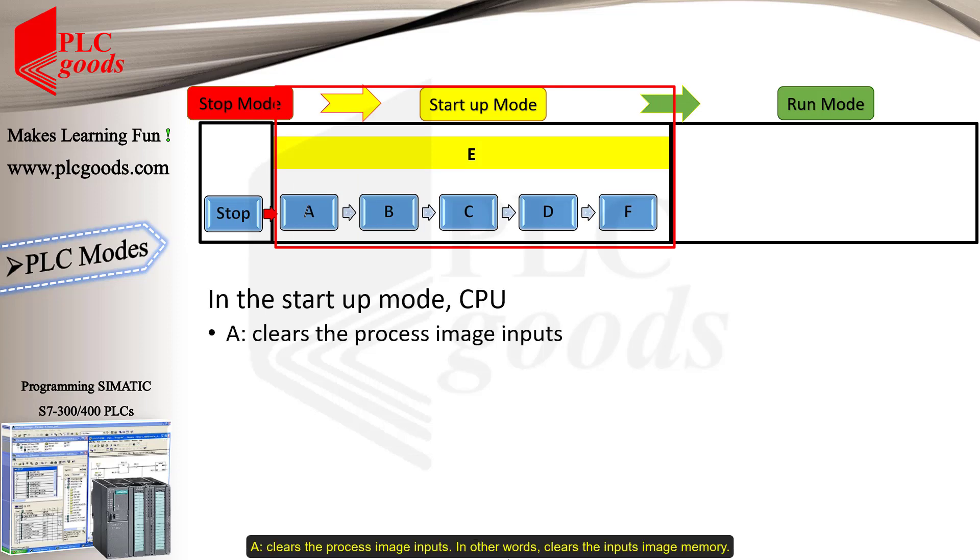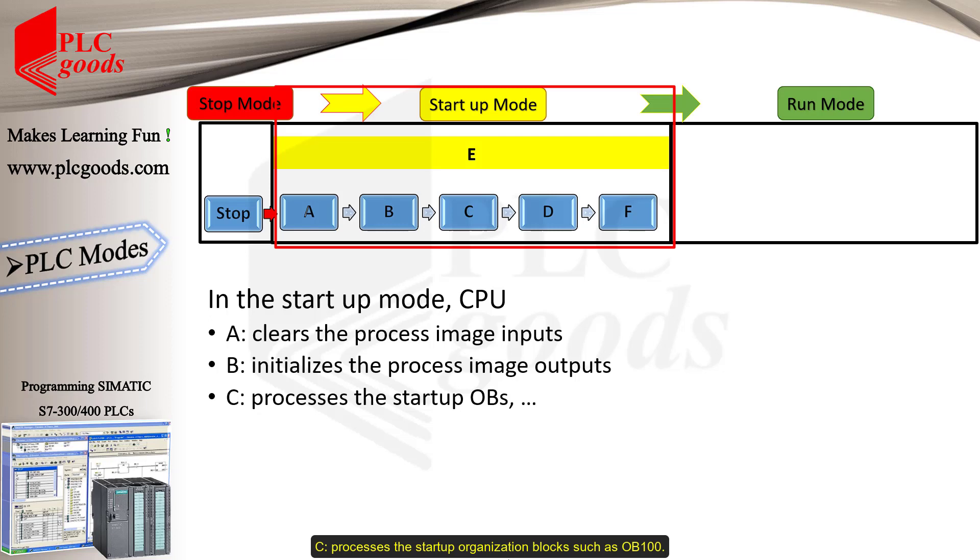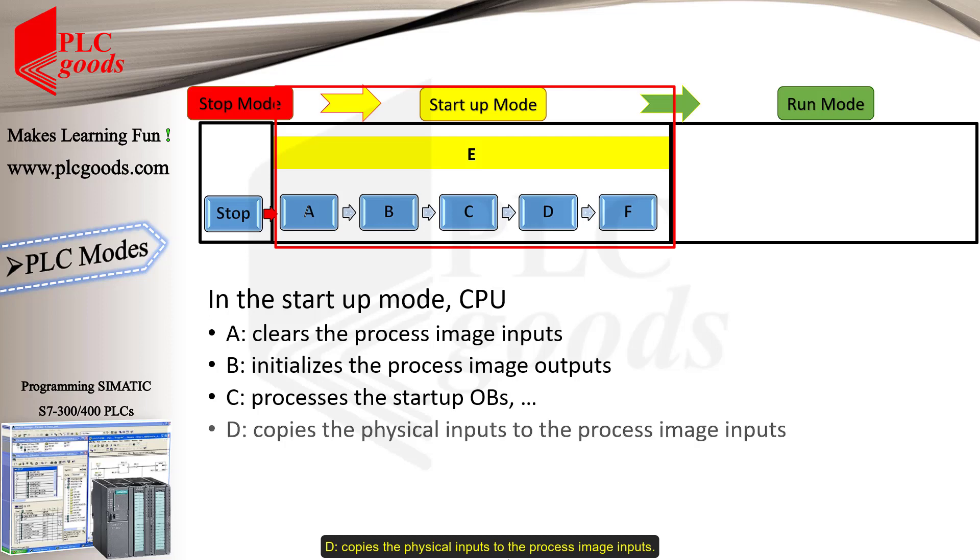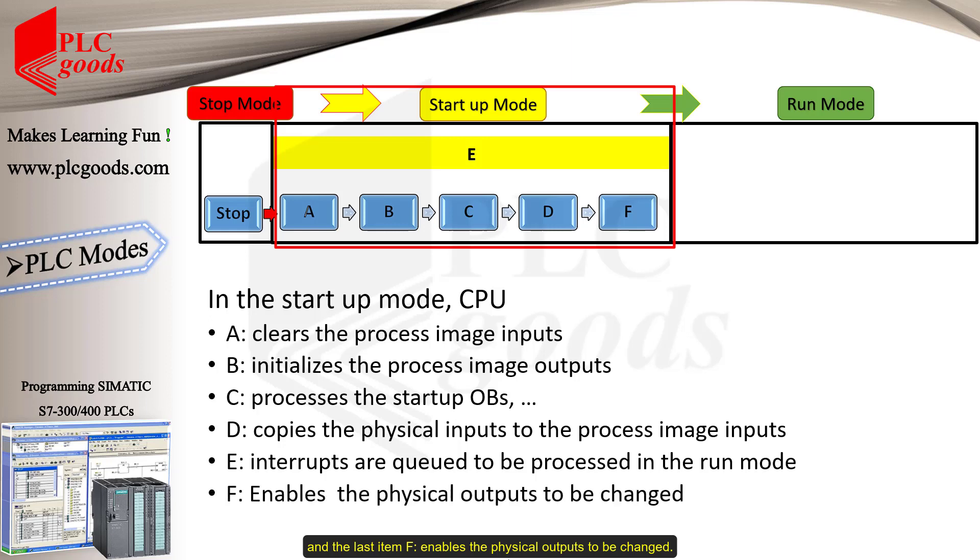As you see, in the startup mode, CPU does six tasks, named with A to F letters. A clears the process image inputs, in other words, clears the input's image memory. B initializes the process image outputs. C processes the startup organization blocks, such as OB100. D copies the physical inputs to the process image inputs. E queues interrupts to be processed in the run mode. And the last item, F, enables the physical outputs to be changed.